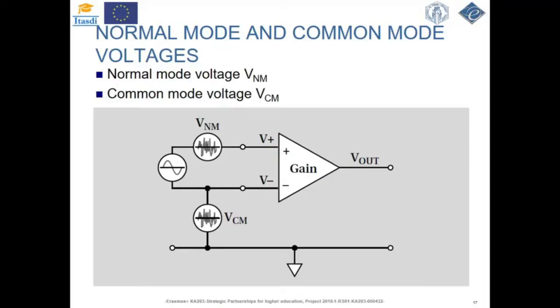One definition of the normal mode voltage, noted as VNM in the figure, is a noise voltage that appears across the inputs of the amplifier and thereby adds to the input. Normal mode specifications are usually given at frequencies or frequency ranges where sources of noise are most common. For example, 50 Hz or 60 Hz, which is the frequency of the power line in Europe or the USA. The measure of an amplifier's ability to reject noise while passing DC and low frequency signals is a parameter called the normal mode rejection ratio.